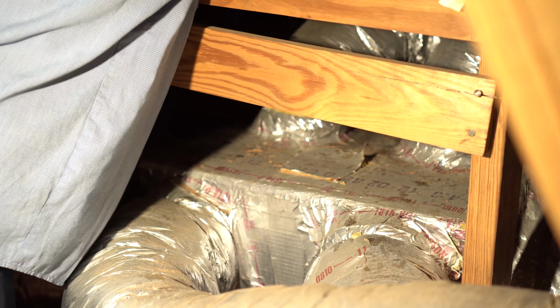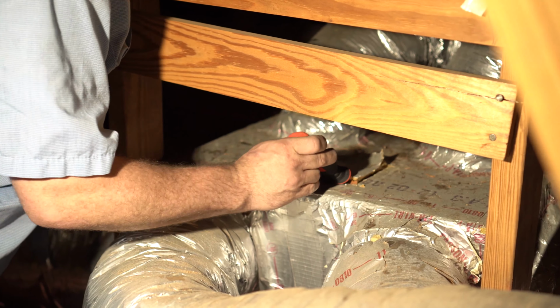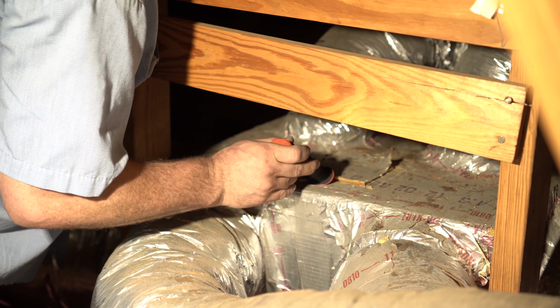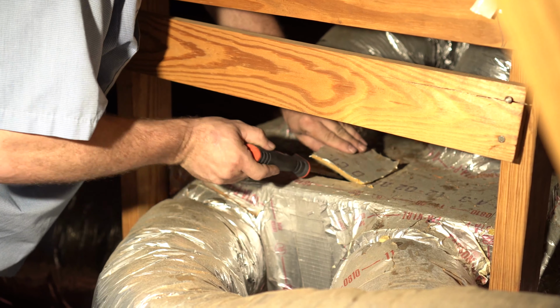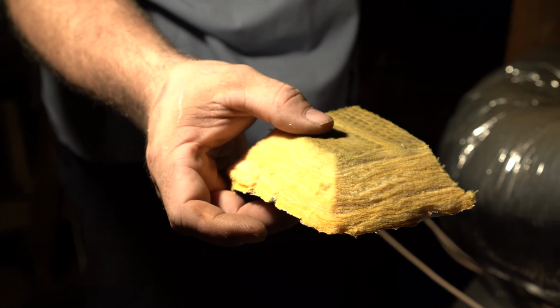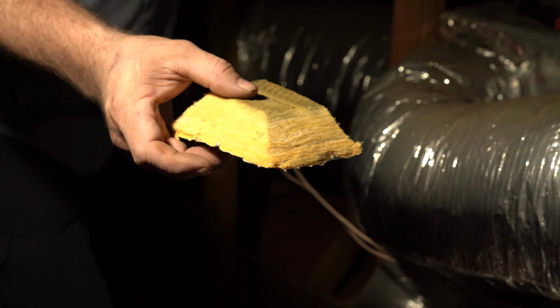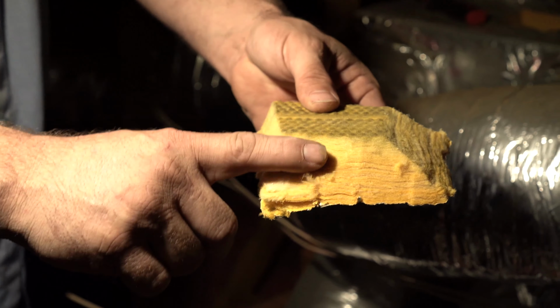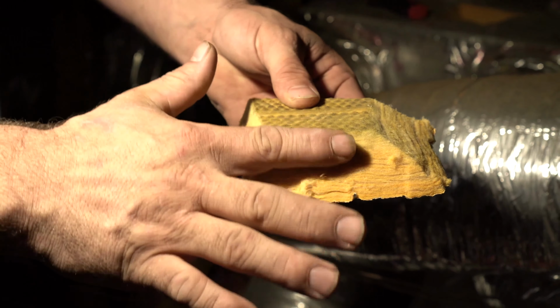When accessing the duct for maintenance, do not cut the duct wall using a straight incision. Straight incisions will cause the duct cutout to fall through the hole when it is replaced, creating a safety hazard and causing damage to the unit. To access the duct, cut the duct at an angle, creating a bevel-formed cutout that will remain in place when it is replaced.